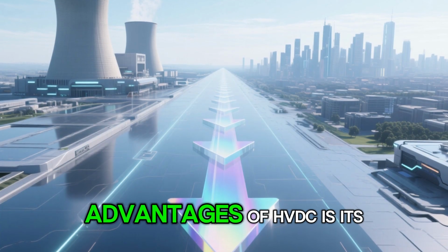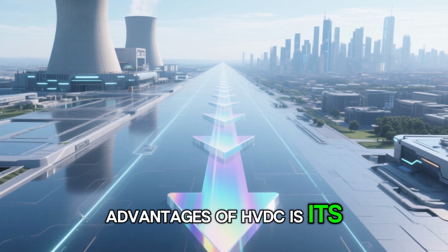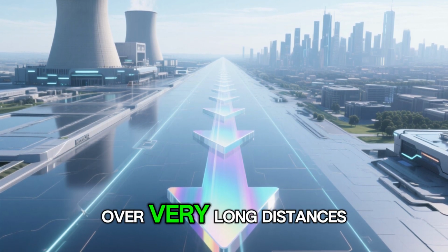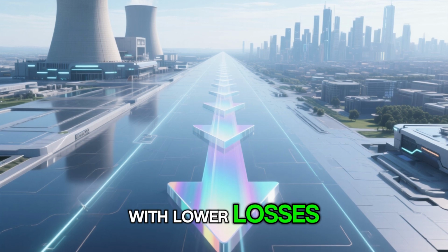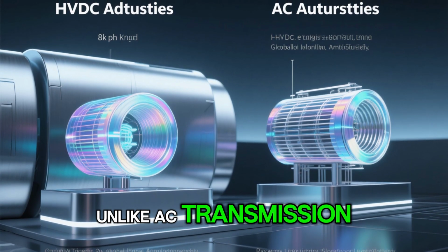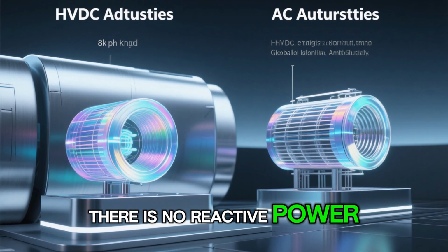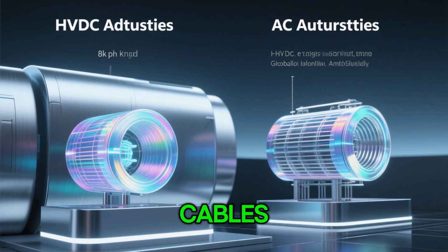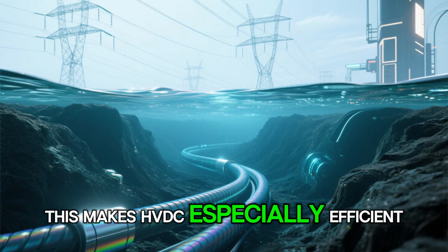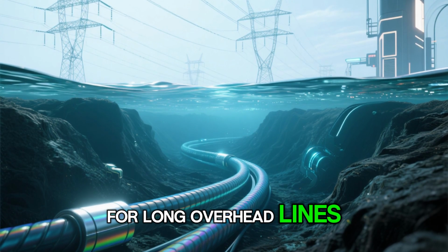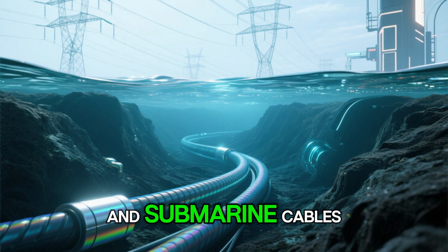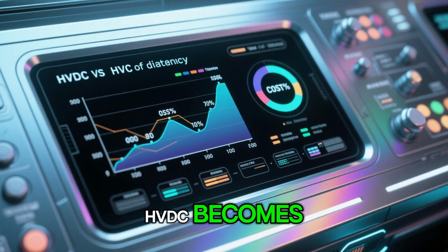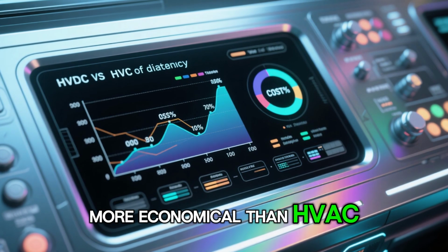One of the strongest advantages of HVDC is its ability to transmit power over very long distances with lower losses. Unlike AC transmission, there is no reactive power, no skin effect in the same way, and no charging current in cables. This makes HVDC especially efficient for long overhead lines, underground cables, and submarine cables. In many projects, HVDC becomes more economical than HVAC beyond a certain distance.